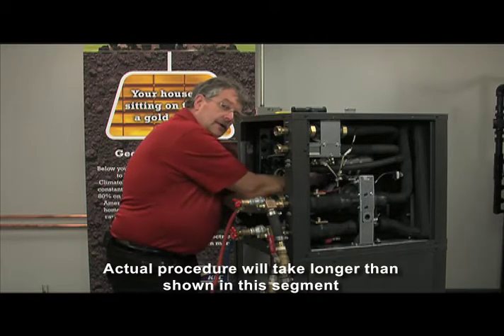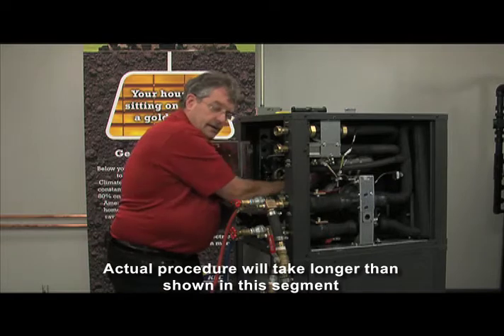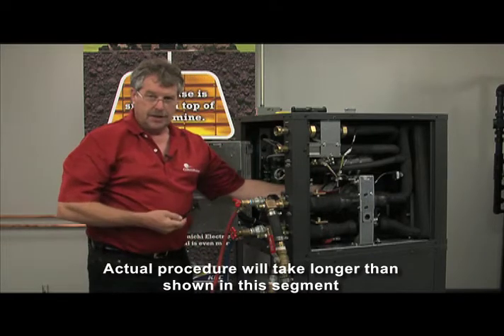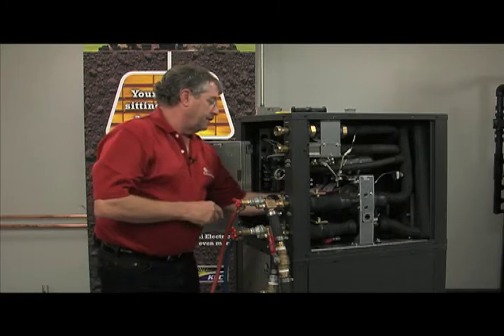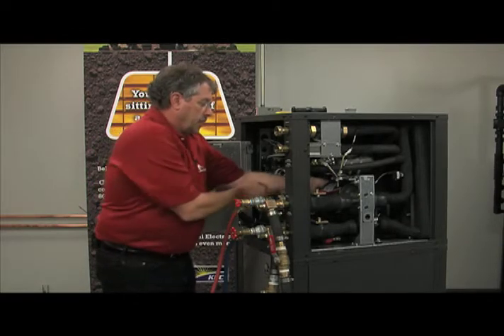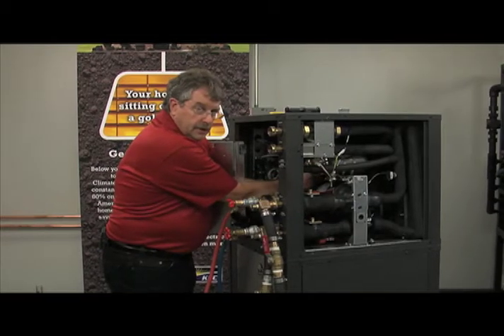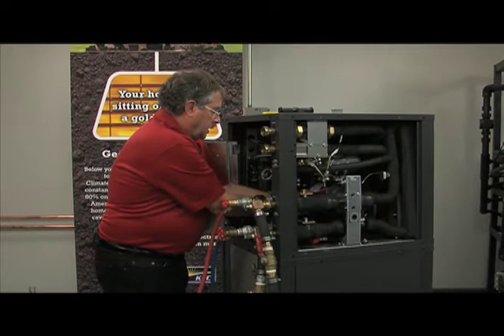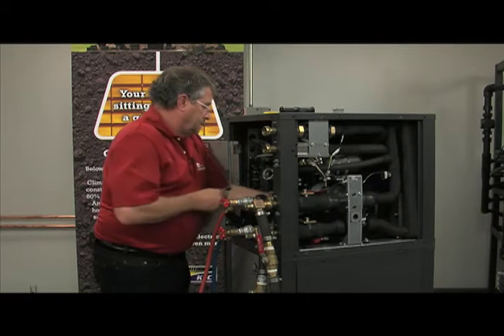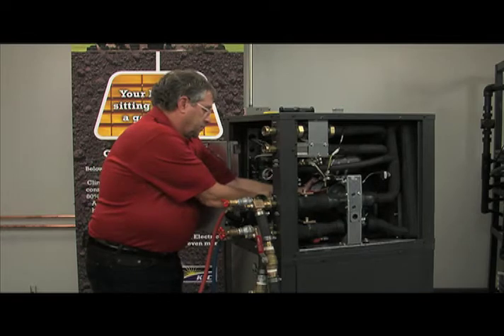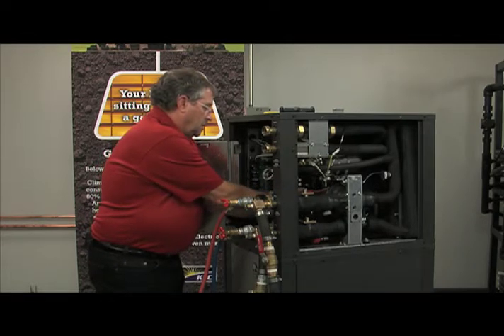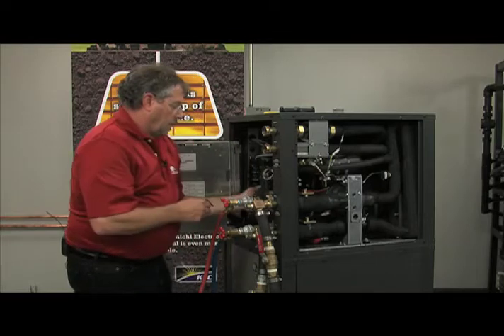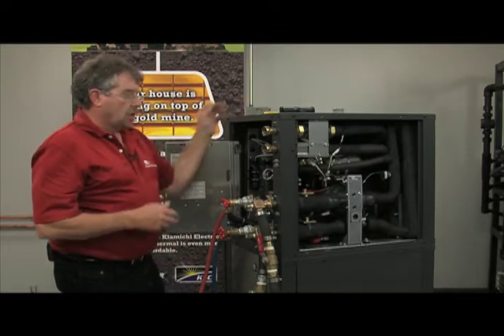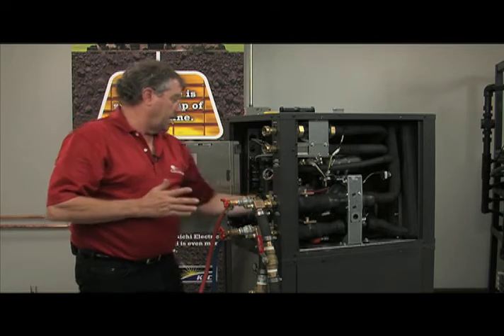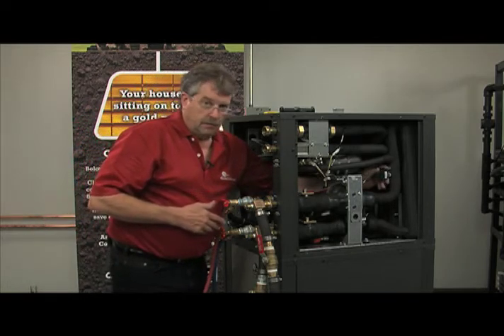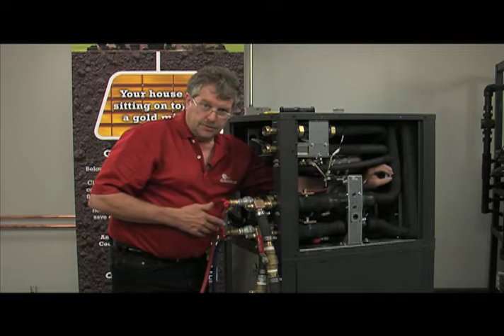Now bear in mind, guys, I haven't taken the pressure down on this unit, but yet I'm taking the screws out of the power head of this pump. By doing that, I'm not breaching the integrity of the water circuit. All I'm doing is similar to how you would remove a module off an ECM blower motor. It's the same thing I'm doing on this pump. So with the power being off for a solid 25 minutes and more, once I have those two screws backed out, not even removed, now I can pop that ECM module off. Again, I have not got into the water side, and now I've opened up an awful lot more room.